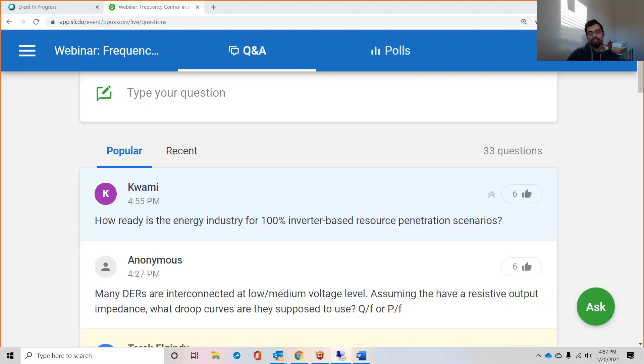For the first question, regarding what kind of droop curves they're supposed to use, it depends on what voltage level they're connected at, how they're going to provide that response, and what type of DER they are—whether a utility-scale plant connected closer to the substation, or a residential rooftop PV. All of that will dictate what kind of droop curves they use.